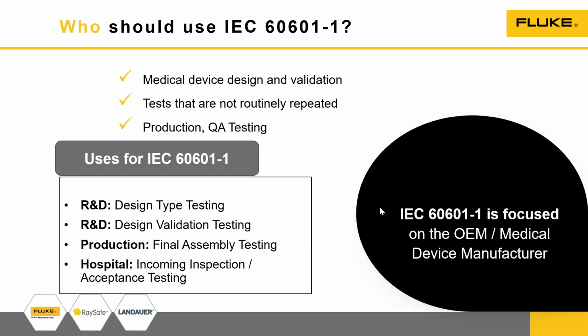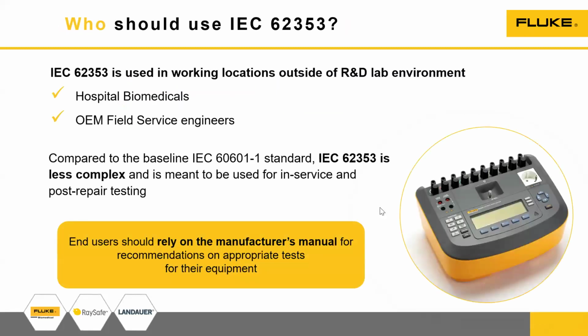Beyond that, the IEC slowly understood that something more was needed. IEC 60601 was more stringent, and for a hospital environment, where tests need to be done repetitively, such stringent testing may not be required. That is when they came out with IEC 62353, mostly for the hospital or the medical device service engineer. It is designed for repetitive and recurrent tests, so that it saves time, can be done much faster, and reduces the chance of the repeated testing negatively impacting the medical devices. That is why 62353 came into the picture.